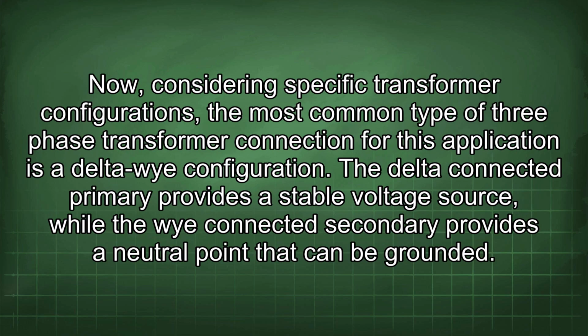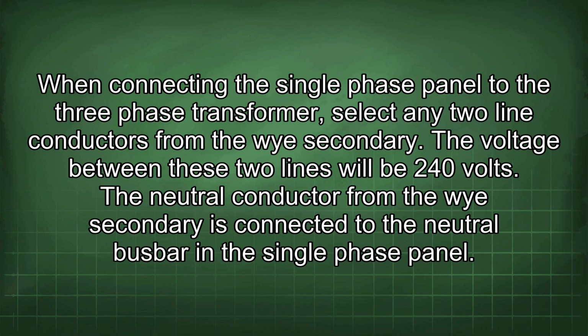Now, considering specific transformer configurations, the most common type of three-phase transformer connection for this application is a delta-Y configuration. The delta-connected primary provides a stable voltage source, while the Y-connected secondary provides a neutral point that can be grounded. When connecting the single-phase panel to the three-phase transformer, select any two line conductors from the Y secondary.